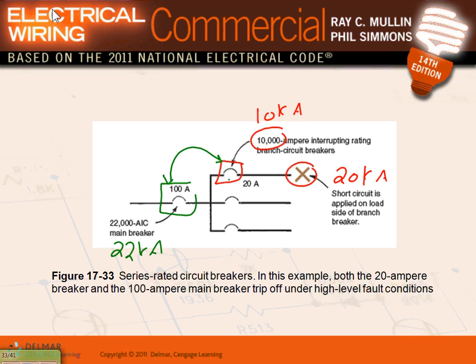So under these circumstances, you really care less about losing the load. Losing the load is not your concern. You want the main to trip. That's a very good point, Chris. This will actually compromise the integrity of the electrical system if you have series rated. A short circuit here could trip the main.